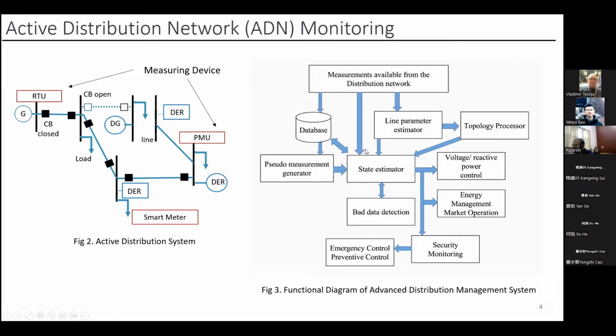Once the estimator gets all this information, it will perform the task and return the estimated states of the system. Using the estimated states, the DSO can take various control decisions such as voltage control or reactive power support; energy management and market operations can also be done. Most importantly, if any of the devices are giving erroneous data, which is a difficult thing to achieve in a distribution system, the state estimator would detect such bad measurements. With the estimated states, the DSO can also perform security monitoring. It can see whether there is overloading in a line, or a voltage dip beyond the permissible limit at any of the nodes, and can take the required emergency or preventive controls.